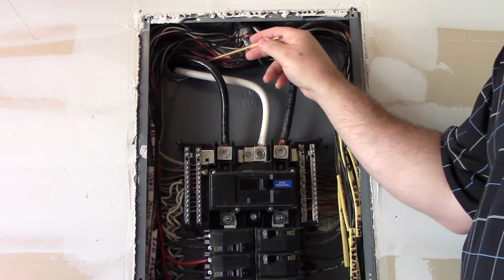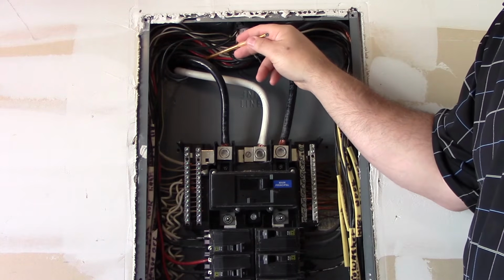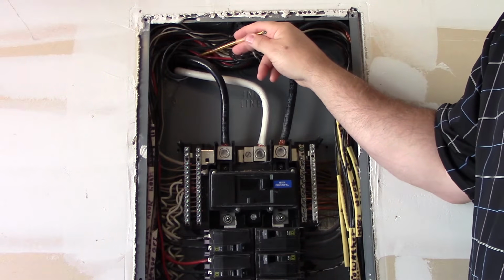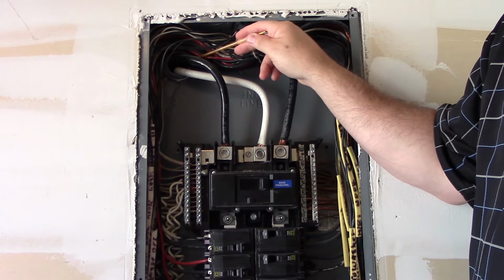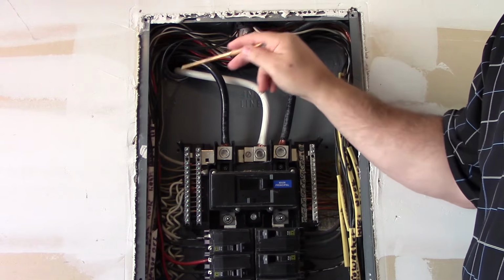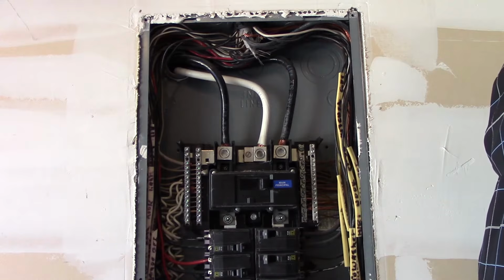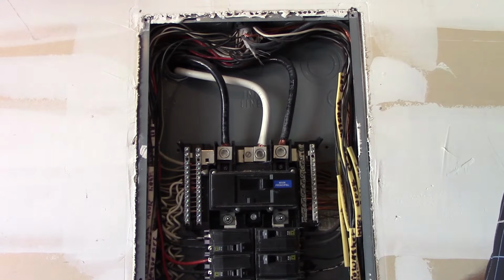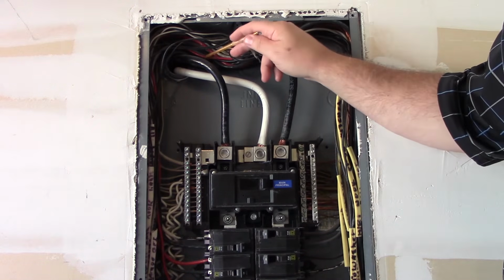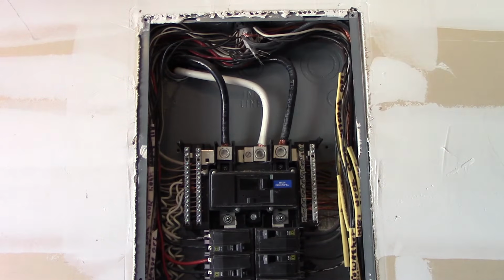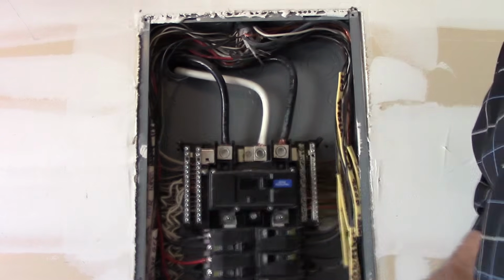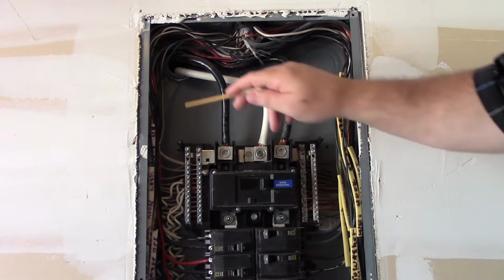And I do notice here that this conductor right here, this wire, looks like it's cutting into this actual insulation right here as it comes in. The good news is this is non-metallic. If it had been a metal one, we have even a bigger concern. But it is non-metallic. But you are required to have a bushing on all raceways in accordance with 300.4(G) of the National Electrical Code. So we have to establish that.